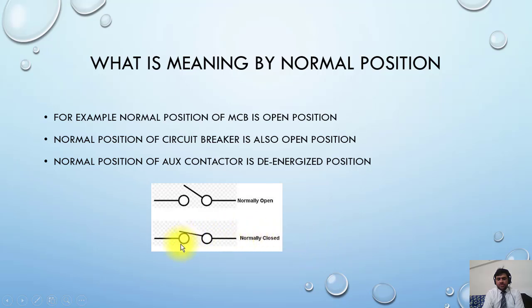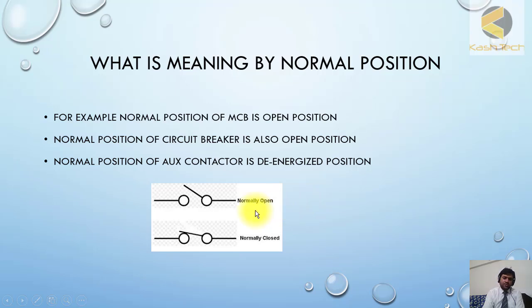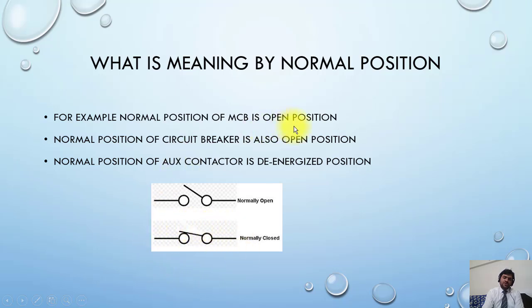As per drawing philosophy, if the MCB is at normal position it will be open; if MCB is at closed position this will be closed. If I make the MCB open and check the continuity, I will find this contact open, and if I check the other contact I will find continuity there.